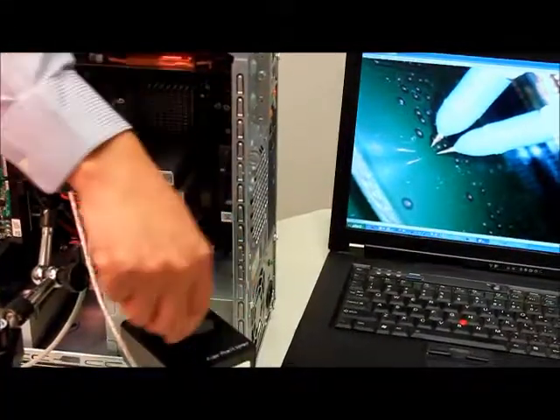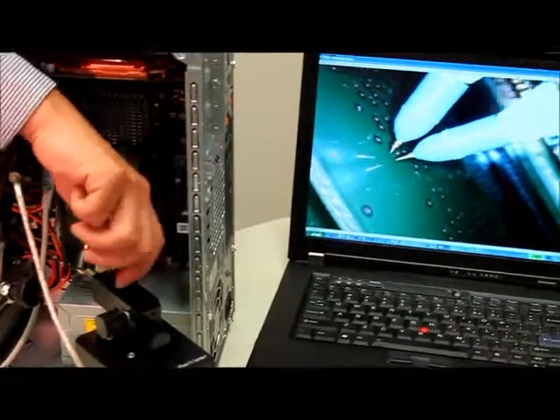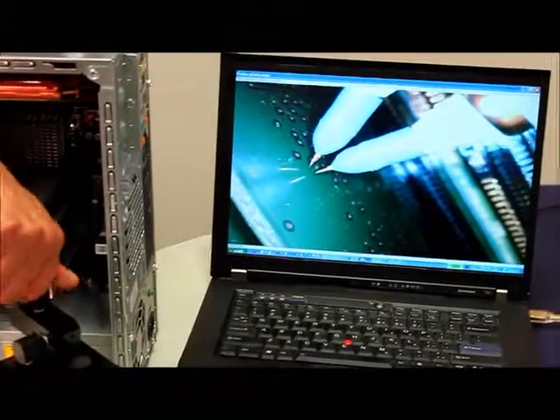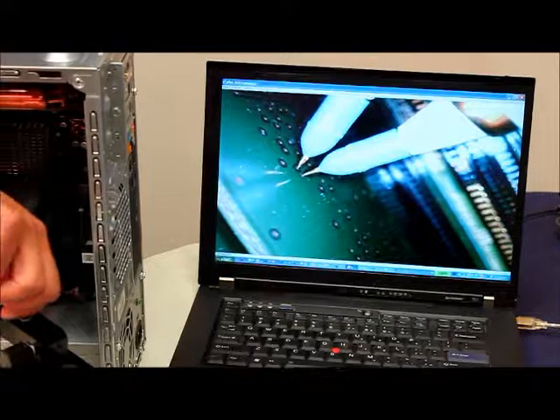Adjust the X, Y, or Z fine adjustments to ensure the probe tips firmly contact the PCB pads.